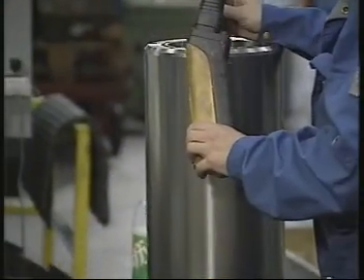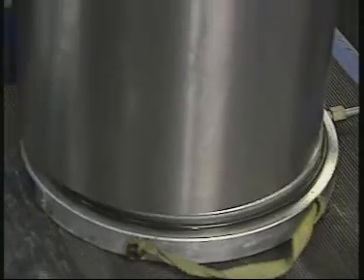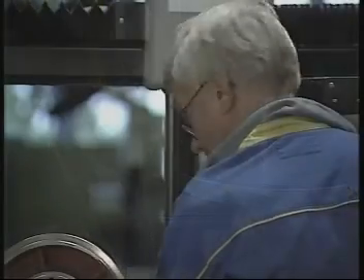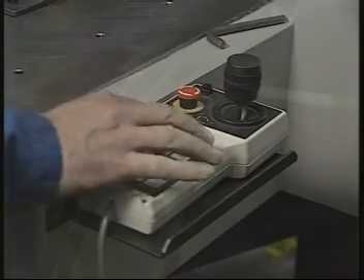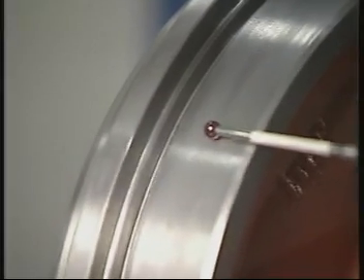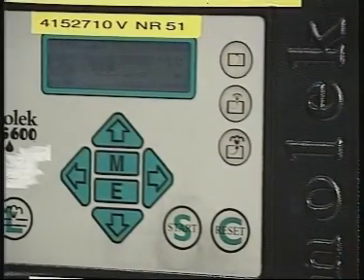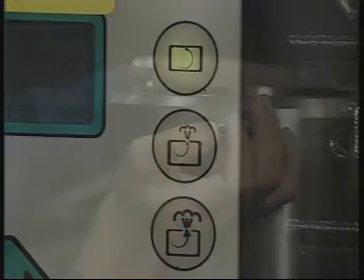Since flammable vapors or liquids are present in many of the environments where mixers are located, explosion-proof mixers, known as EX-approved mixers, are strongly recommended. The explosion-proof version is designed for use in explosive environments in accordance with Factory Mutual standards. All interface areas between components are very narrow, so it becomes impossible for sparks to escape to the surrounding medium. EX-approved products are also designed to withstand high inner pressure. A good indication of how well we've done with the EX-approved Flygt mixers is the American Bureau of Shipping's stamp of approval.